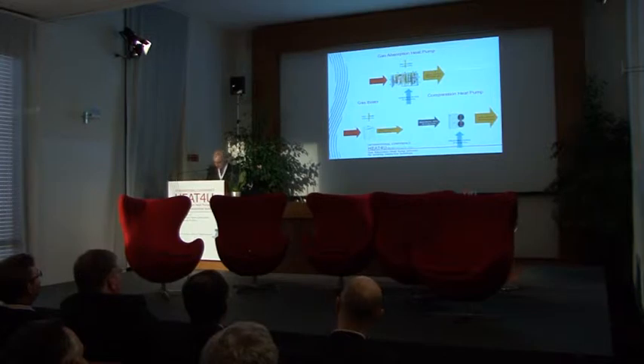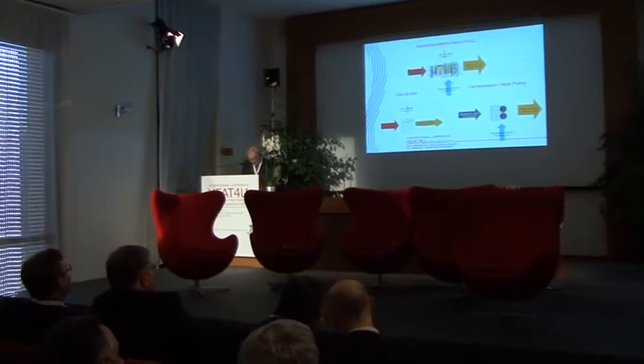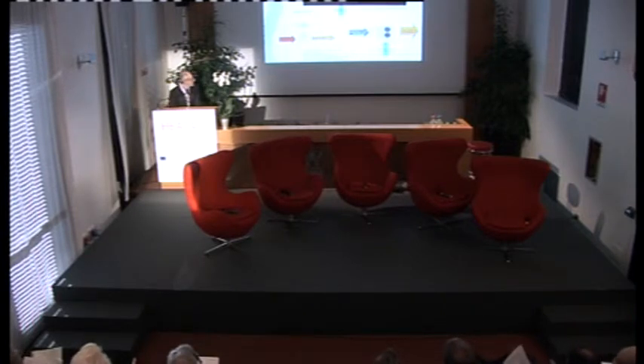And this is the gas absorption heat pump. It's a device in which heat, not mechanical energy, heat drives a thermodynamic cycle to pump heat from a low temperature source, for example, outdoor ambient air, to a higher temperature sink, for example, the water loop of a hydronic heating system. When applied to a heating system, a gas absorption heat pump device delivers the heat output at an efficiency much higher than a conventional gas boiler. And the useful output heat is the sum of the heat input plus the heat pumped from the low temperature source minus the flue gases. The useful output heat is higher than the driving input heat, while in a conventional boiler, the useful output is always lower than the input. So this is to generally depict how this different technology works and the energy fluxes.